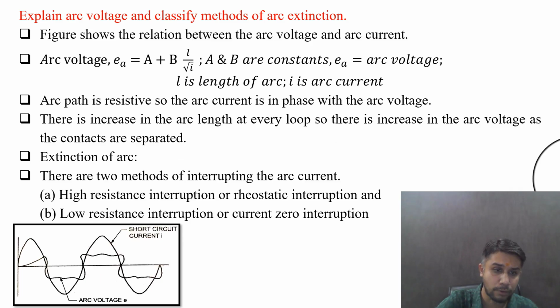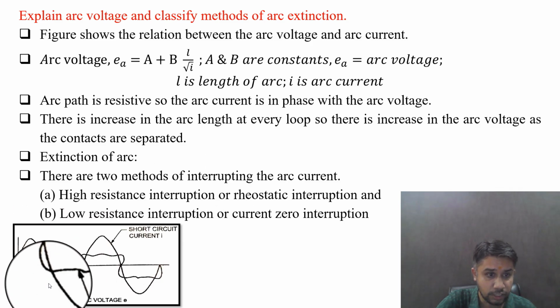So in the figure, you can visualize the relation between the arc voltage and arc current at the time of short circuit. This is the short circuit current, that is the arc current, and this is the arc voltage. So arc voltage is given by the equation E = A + B L / √I, where A and B are constants, E is the arc voltage or EMF of the arc, L is the length of the arc, and I is the arc current magnitude.